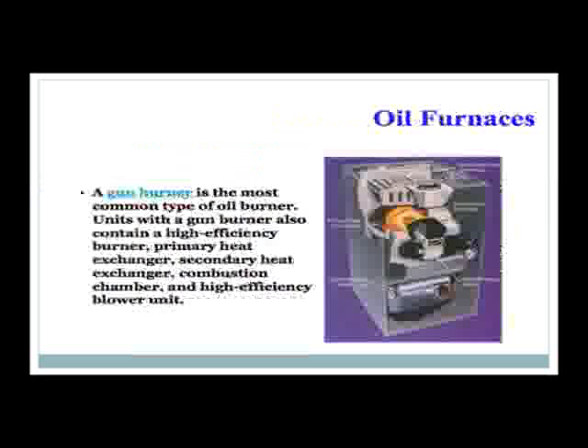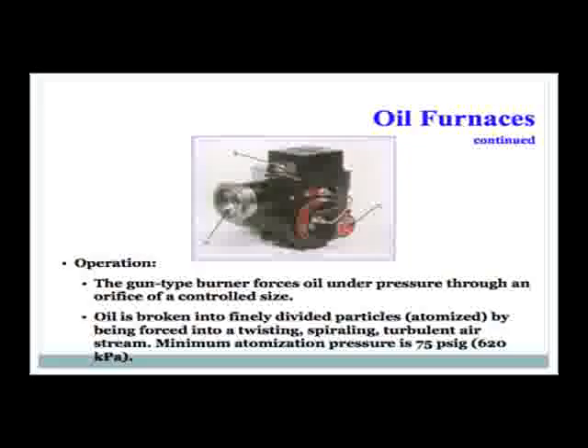A gun burner is the most common type of oil burner. Units with gun burners also contain high-efficiency burners, primary and secondary heat exchangers, a combustion chamber, and high-efficiency blower units. The gun-type burner forces oil under pressure through an orifice of a controlled size. Oil is broken into finely divided particles that are atomized by being forced into a twisting, spiraling, turbulent air stream.